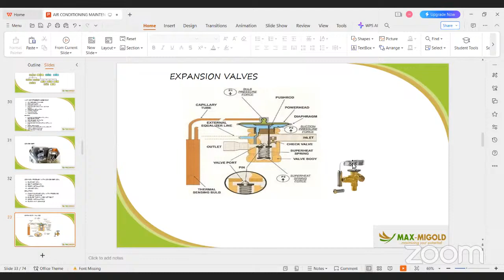The standard form of installation is that when you are brazing, nitrogen is running through all your refrigerant pipes. When you are brazing, nitrogen does not explode, so you need to take cognizance of that. But if you can pump down, then fine. You can braze and do what they call pressure testing before you connect. If not, there will be issues. Once the dirt is cleared, the coast will be clear for your AC to work well.